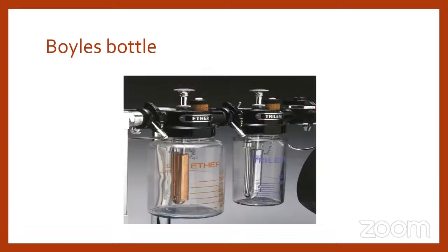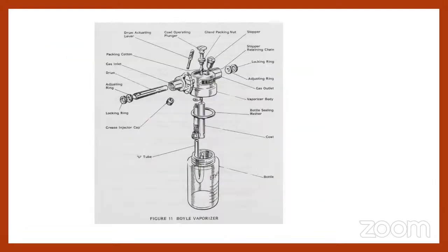Coming to the various types of vaporizers, the first one is Boyle's bottle. It is a multiple agent type, which means we can use several agents like ether and trichloroethylene. These liquids will be poured into the bottom jar. It is a flow over or bubble through type. You can see the various parts of Boyle's vaporizer in this. It basically has a container or a jar which contains the anesthetic agent in liquid form, and it has a U-shaped tube through which the fresh gas will enter the chamber.